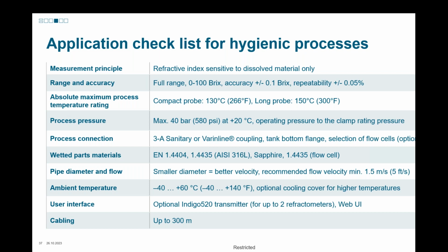Almost an eye chart, again, just showing you the application checklist for hygienic processes. Again, refractive index is sensitive to the dissolved materials only, and is not affected by bubbles or color. Range, expected accuracy, again, typically 0.1%. We have very good repeatability.